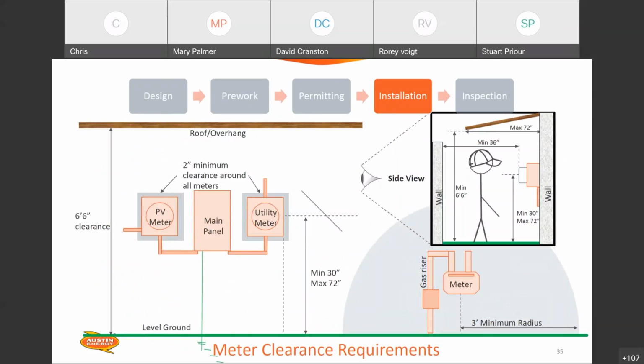Alrighty, so the installation. Here we have your main panel and your 2 meters. You've got your 2 inches around each meter, as we've discussed. So 6 feet to the top of that meter is going to be your upper limit, and no lower than 2.5 feet on the low side.